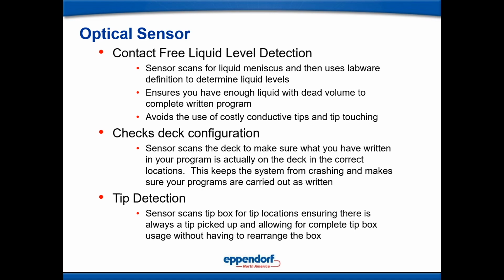Our machine uses a confocal infrared laser to reflect off of the meniscus. It records the meniscus height. It goes into the labware definition, which has a means to calculate the residual volume. So without touching anything, it knows how much is there. Why is this important to you? Well, if you're going into an unknown container, you don't have to touch that liquid to dispense close to the surface and then not have to change your tips afterwards.